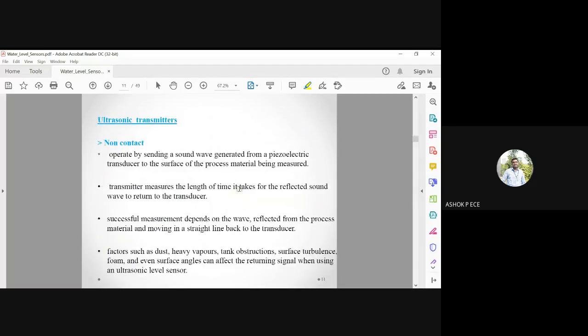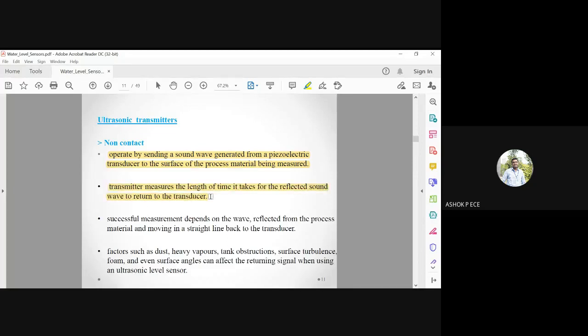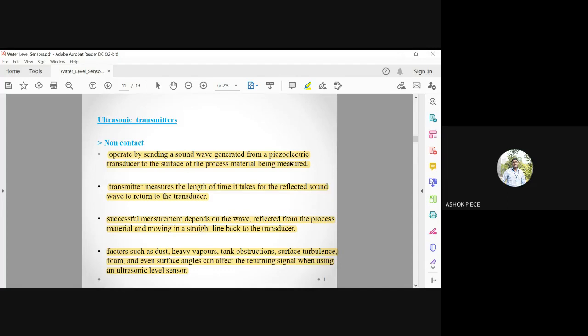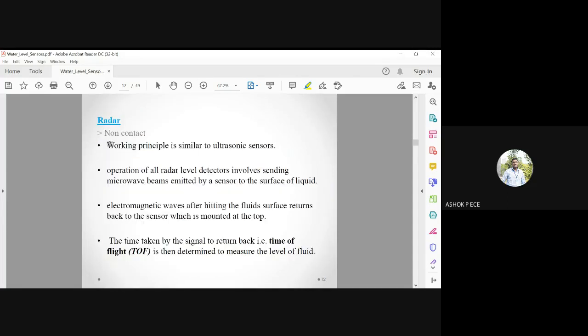For non-contact devices, an ultrasonic transducer is mounted at the top of the tank and sends a sound wave downward. The wave hits the water surface and reflects back; the transit time is used to calculate the distance and thus the water level. Since the sensor is mounted at the top, water never touches it — making it a non-contact type. It periodically measures the water level and sends a signal to turn the motor on or off accordingly.